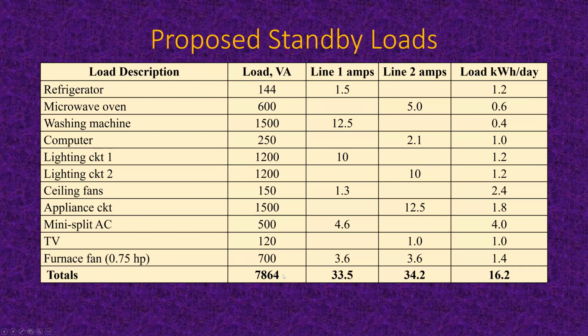7,864 volt amps of loads connected. Line 1 and line 2 more closely balanced at about 34 amps each, and a load of 16.2 kilowatt hours a day. In other words, just about twice the size of what we had before. And in fact, the array size this time is about twice the size of the array we had before. So you can see that whether you work it frontwards or backwards, you're still going to get pretty much the same result. And so this means if this is all we can do with that roof, then this is what we can do on a battery backup system in terms of standby loads. So you can do the calculation and know ahead of time what you might be able to expect.